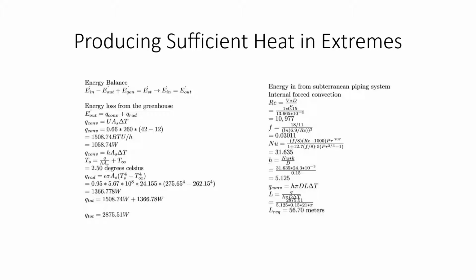All right, so we ran some numbers trying to figure out how exactly this was going to work. In this hypothetical situation, we have the coldest night of the year in Rexburg, Idaho, which last year got down to negative 11 degrees Celsius, which is 12 degrees Fahrenheit. We use the difference between the 30-foot temperature, which is 10 degrees Celsius, and the negative 11 degrees of the night. So we have a delta T of 21.